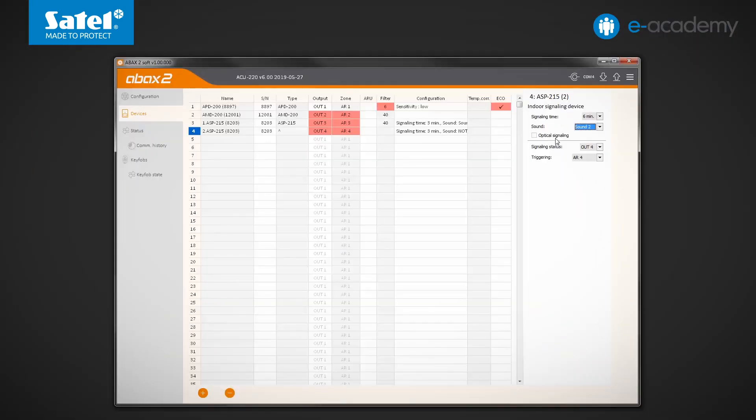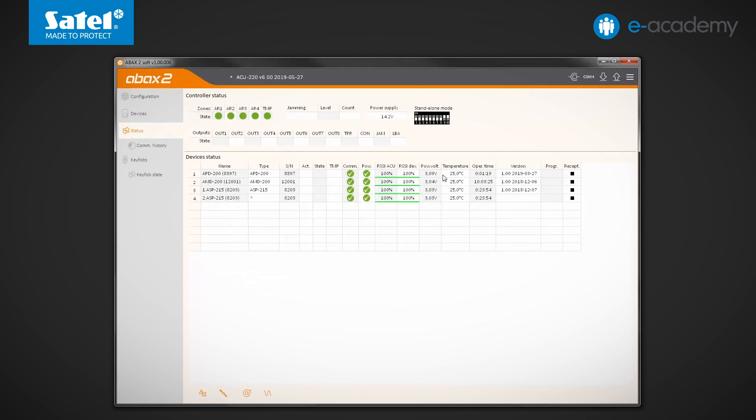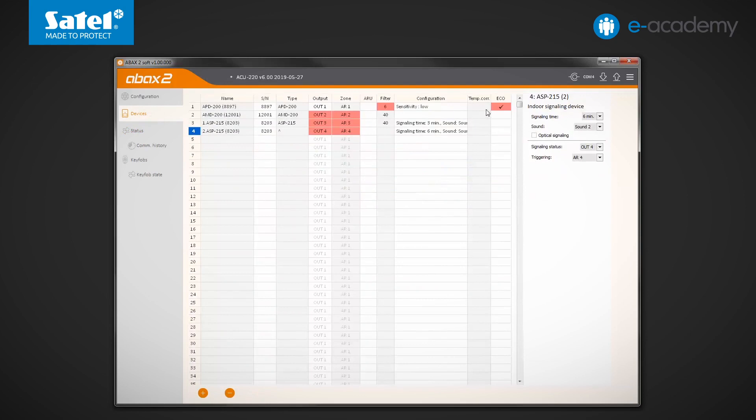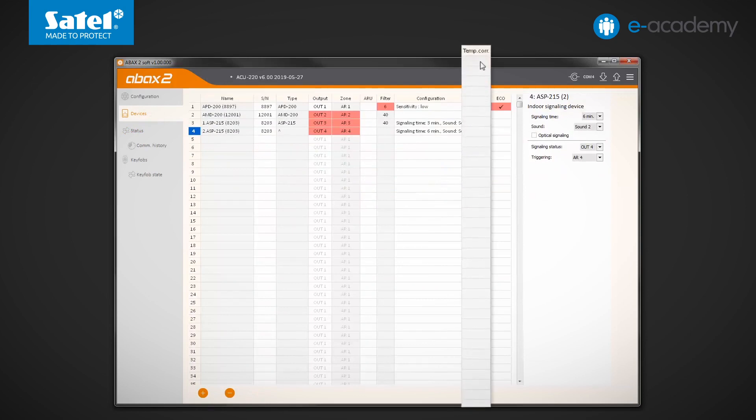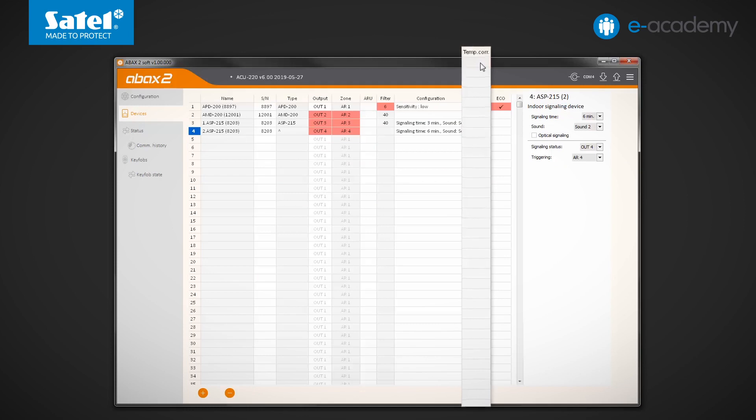Some of the ABAX2 system devices send the ambient temperature information to the controller. You can check the current temperature values in the status tab. If it turns out that the temperature indications should be corrected, then in the column second to last of the device table, you can set a correction ranging from minus 3.5 to plus 3.5 degrees Celsius.